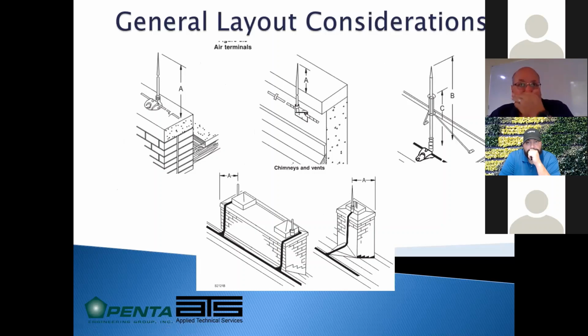I'm going through a lot of these things because we see a lot of companies install lightning protection systems, but we see very few maintain them. And when we're on top of roofs looking at other things, we're seeing just a lot of damage to the existing systems. And if the existing system isn't functioning properly, providing that preferred pathway to ground, then it's going to allow lightning energy to go into the building where we don't want it. And so maintaining the system is very important to ensure that it's working properly.